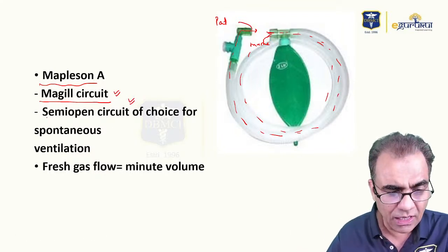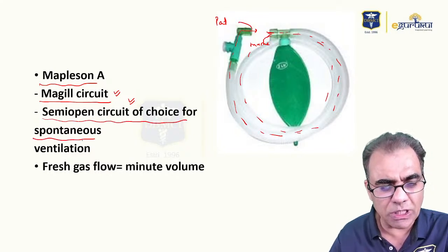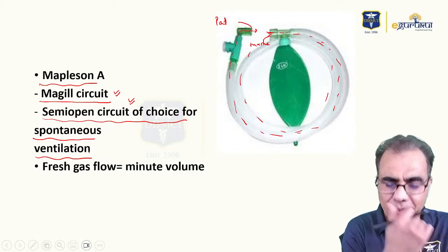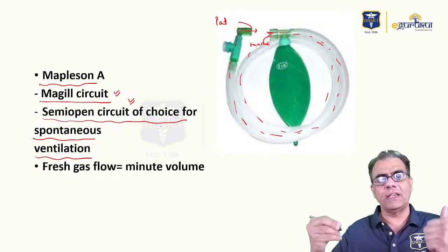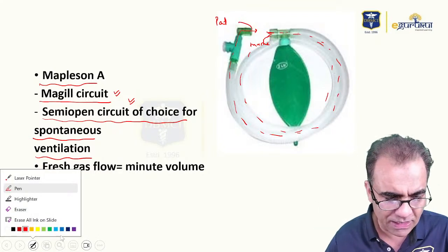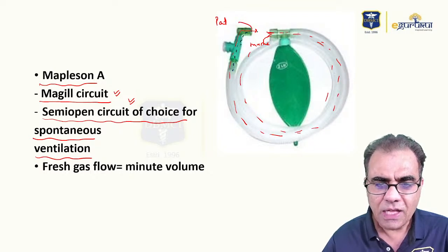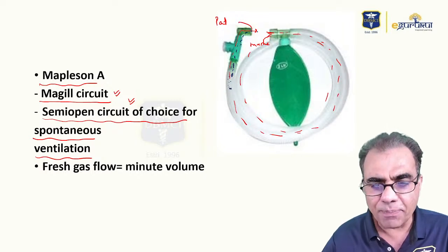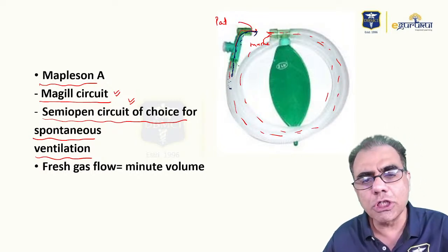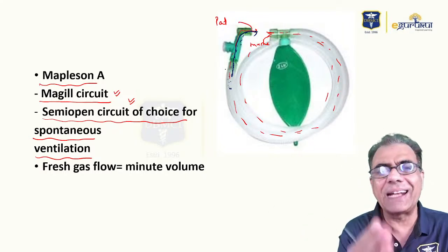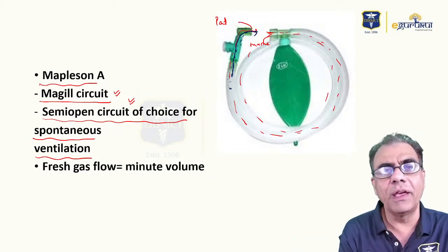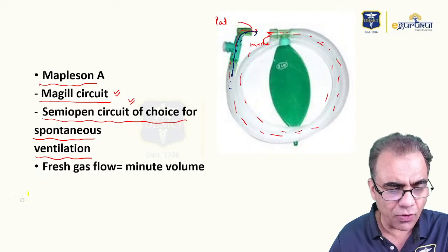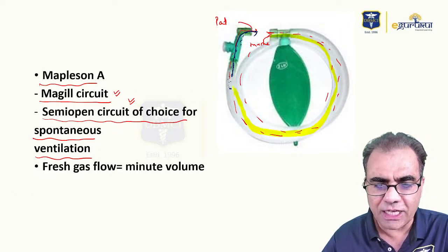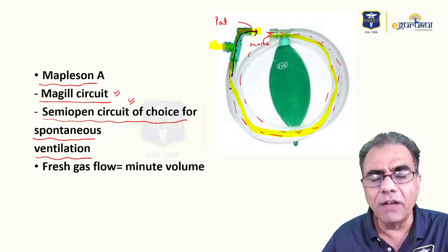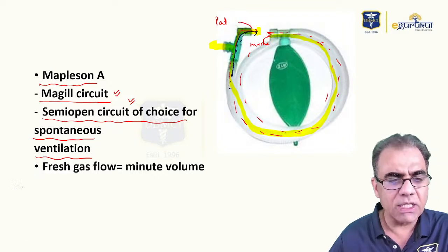We are discussing the semi-open circuit. It is the semi-open circuit of choice for a patient who is spontaneously breathing. See, now the problem with every circuit is that when the patient expires, for example, say this patient is expiring, these are expiratory gases. These expiratory gases may get retained in the tubing and the patient may re-inhale these gases again. This is called rebreathing. So the aim of every circuit is that there should not be any rebreathing. To prevent rebreathing, you have to set a fresh gas flow which should be sufficient, first to push these expiratory gases out of this expiratory valve and then to be delivered to the patient. The fresh gas flow recommendation for the Magill circuit is that it should be equal to the minute volume.